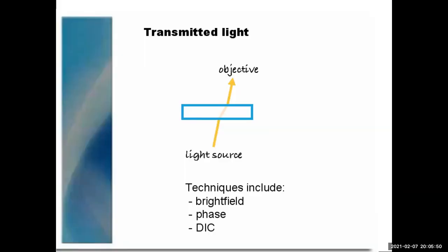Let's look at transmitted light. The light has to go through the specimen itself, which has to be fairly thin — hence microtomy, hence histotechs. Either choose a thin specimen or have a histotech cut it for you. The light source is on one side of the specimen and the objective, which collects the light and the image, along with your camera, are on the other side. Techniques that use transmitted light include regular bright field, phase, and DIC.